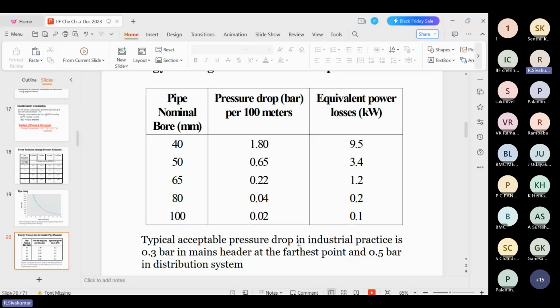What is the generation pressure? For example, 7.5 bar is the air generation pressure. At the air dryer output, there should be only 0.2 to 0.3 bar reduction. If it is more than 0.5 or 0.6 bar, there is a huge scope for energy saving, because some maintenance activities need to be done. From the generation side we are also losing. A pressure drop of 0.5 to 1 bar is very, very critical and alarming.